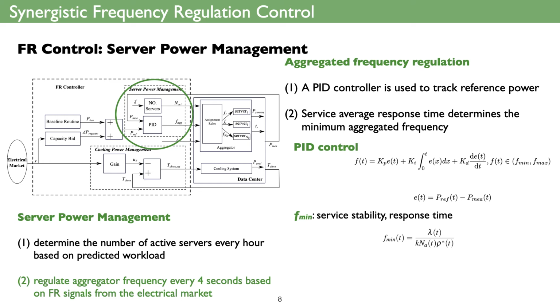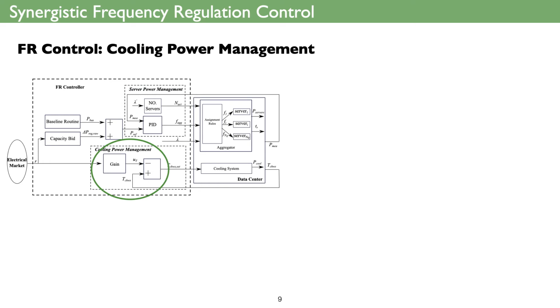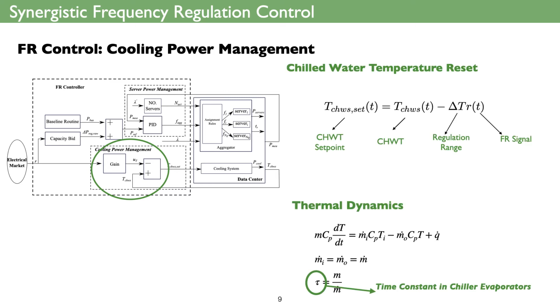So it actually means the quantity of service has to be satisfied even during frequency regulation. The maximum frequency, we use the nominal frequency of the server, which is normalized as 1 in this case. The other power management module is a cooling power management module, where we continuously adjust the cooling system power by resetting the chill water supply temperature set point. This equation shows how we reset the set point based on the baseline supply temperature, the regulation range we predefined, and the regulation signal.